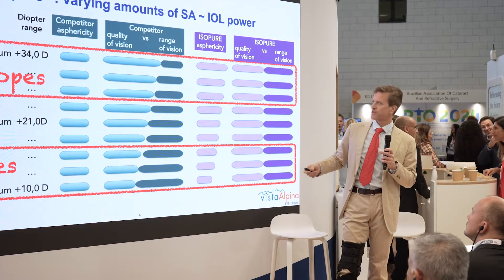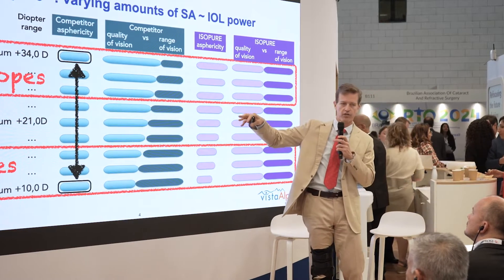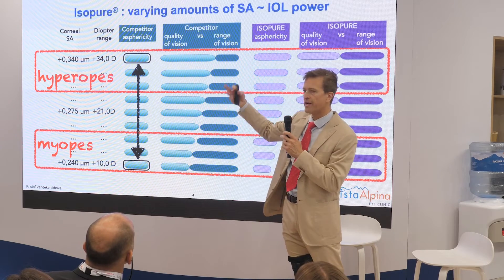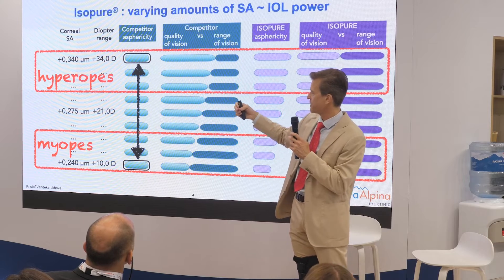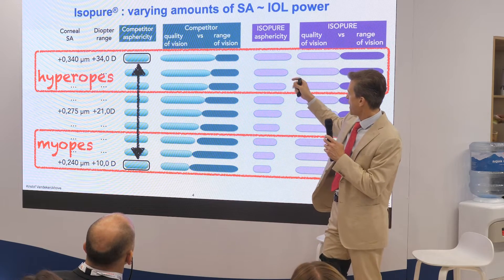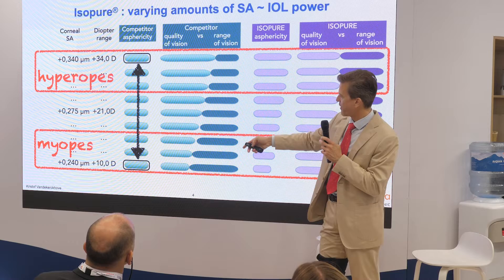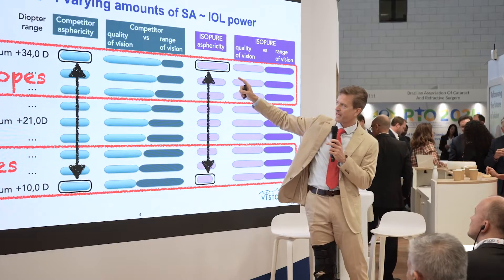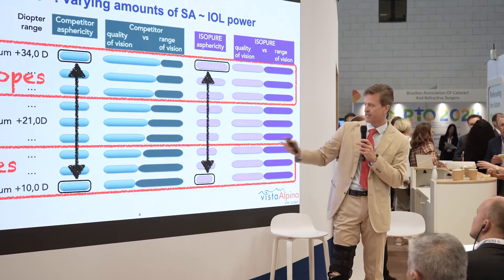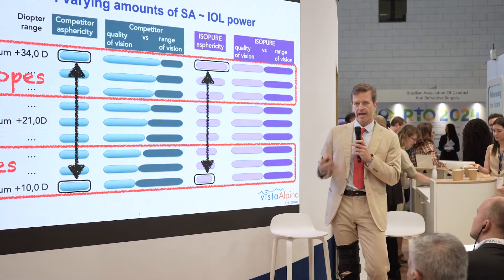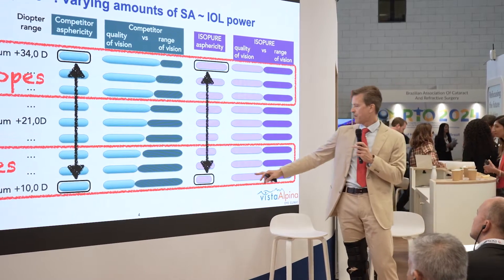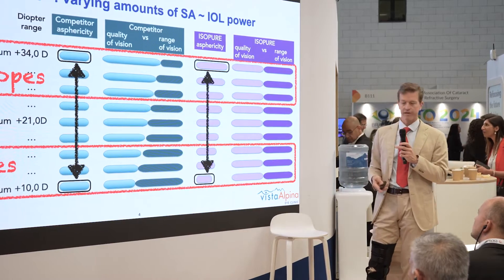According to IOL power, if we take two extremes: an extreme hyperope's cornea in general will have more positive asphericity, and the myope on the other hand will have less. Isopure nicely balances that — more negative asphericity for the high hyperopes, which makes sense, and less for the myope. So isopure can nicely balance defocus and quality of vision across the entire spectrum.